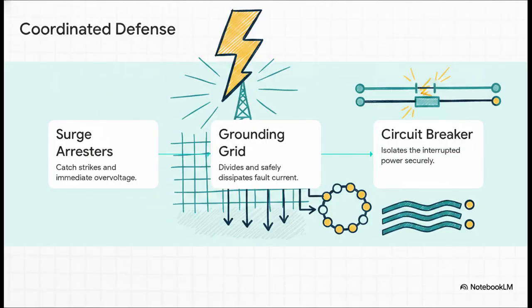So how do we actually survive all that? Well, it takes a coordinated physical defense. First, line entrance surge arresters catch the immediate lightning strikes. Second, that buried grounding grid divides the fault current. And third, redundant circuit breakers slam open to isolate the interrupted power.